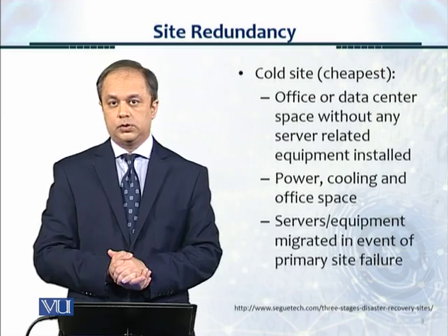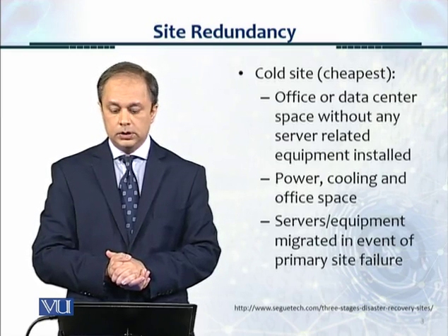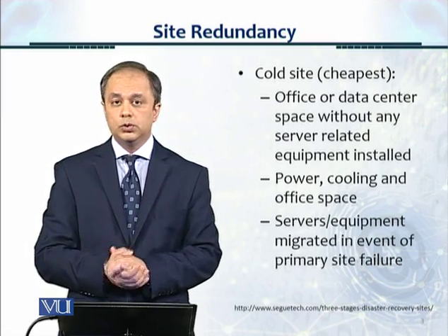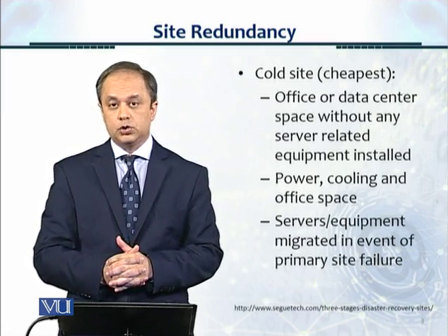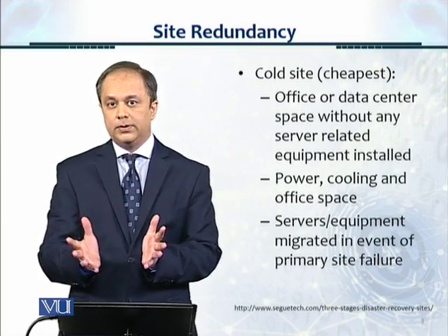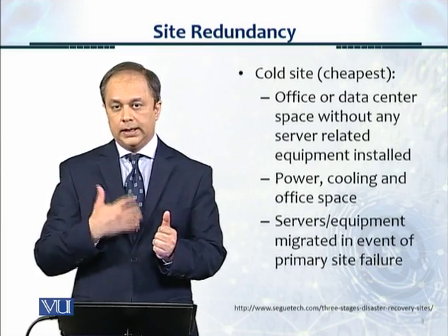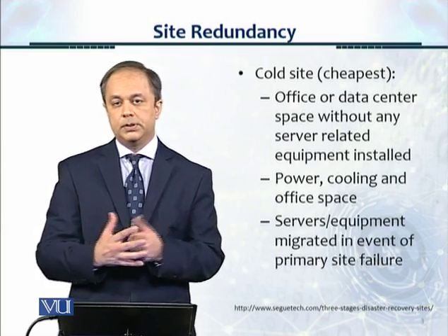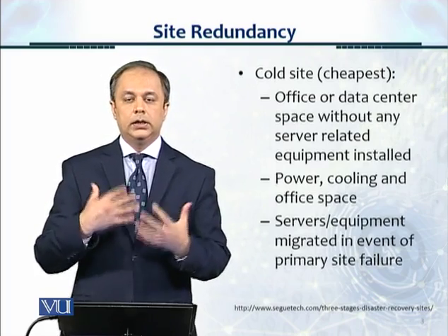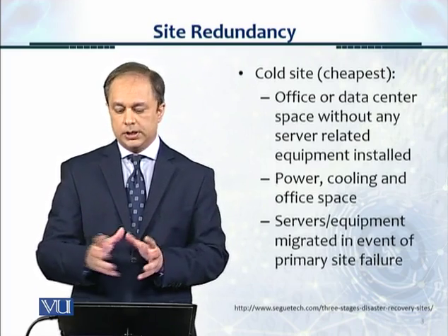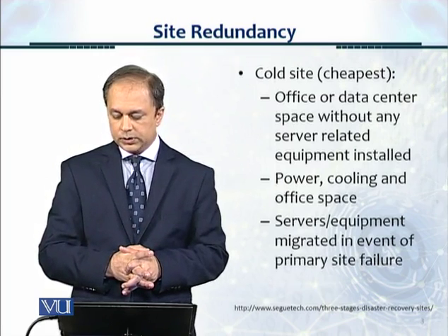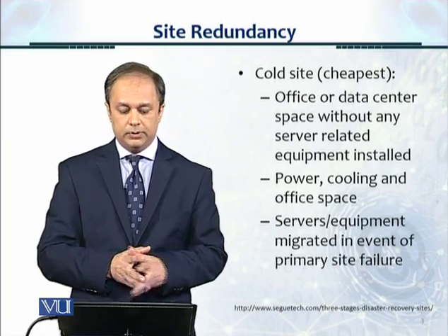At the other extreme is the cold site, which is the cheapest option. Here you have an office or data center space but no servers and no IT equipment installed — that's why it's called a cold site. You have the facility with racks ready, so if a disaster or failure happens at the primary site, you can quickly bring in the IT equipment and set it up. Power, cooling, and office space are available, but servers and equipment are migrated in the event of primary site failure.